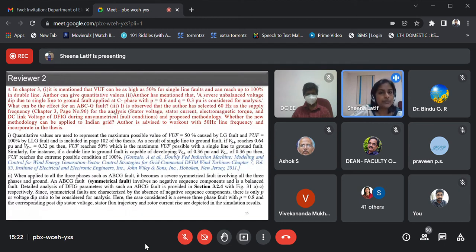I have mentioned that the VUF can reach a maximum of 50% during single line to ground fault and a maximum of 100% during double line fault. So it was asked to give a value. I have included that value as a representation in the thesis. And we have also discussed a VUF equal to 50% in our results shown.